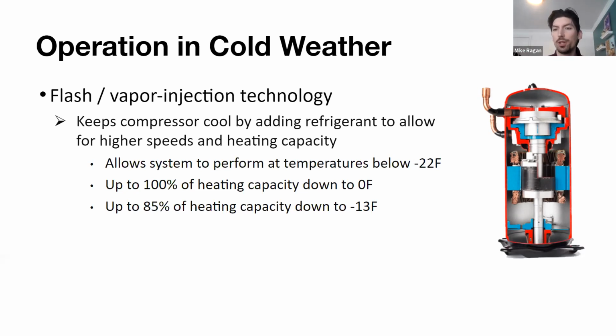That means no derates whatsoever. That means that at 0 degrees, the system is operating the same as it's operating at 40 degrees. With this, we could even get up to 85% of heating capacity down to -13 degrees. If we're talking about the New England climate, -13 degrees is an extreme temperature, unless you're talking about the northernmost parts of Maine, New Hampshire, Vermont, and we certainly have installations there as well. So please don't rule out heat pumps or VRF in those climates. Even in those climates, our systems are going to have very, very minimal derates associated with them.